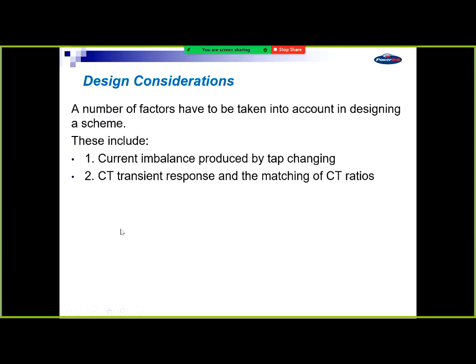There's a number of factors that you need to take into account when you're designing these. There's the current imbalance by the CT, but also by the tap changer on your transformer, and the transient response of your CTs. It's not only the normal current flowing through, but when you get an external or internal fault, more so an external one, you're going to get a lot more current and a transient performance on your CTs. If they're mismatched, that causes an unbalance of current in your secondary. You don't want to trip for external faults, it's external. Internal, you do want to trip. So you do need to be over the top of those.